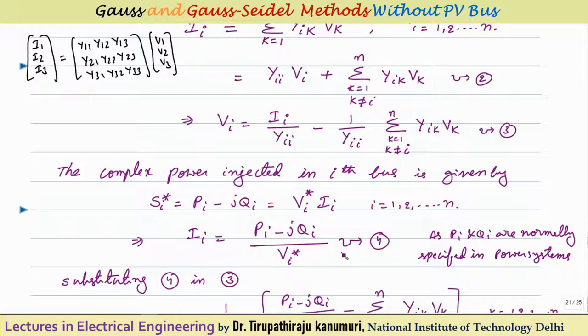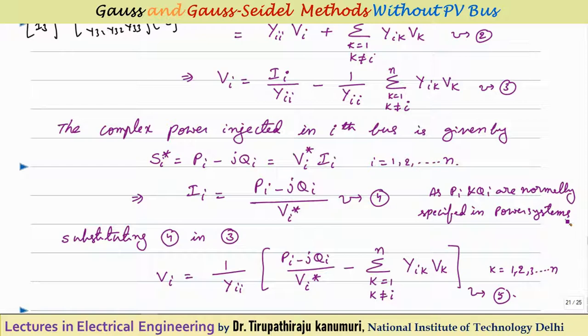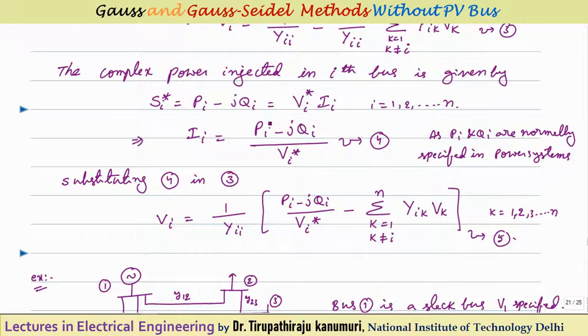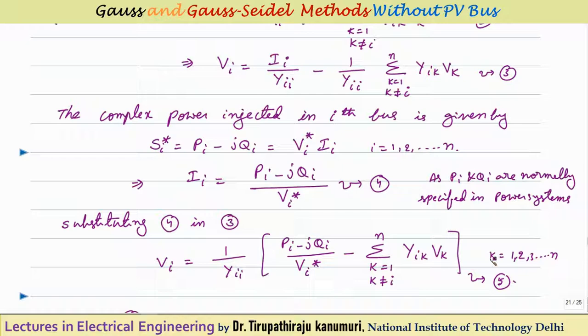Pi and Qi are normally specified in power systems because most buses are load buses — we already know their values. Substituting Ii = (Pi − jQi)/Vi* into the voltage equation gives: Vi = (1/Yii) · [(Pi − jQi)/Vi*] − (1/Yii)·Σ(k=1 to n, k≠i) Yik·Vk. The equation for Vi depends again on Vi itself, which is why we use an iterative method to calculate the voltages at all buses.